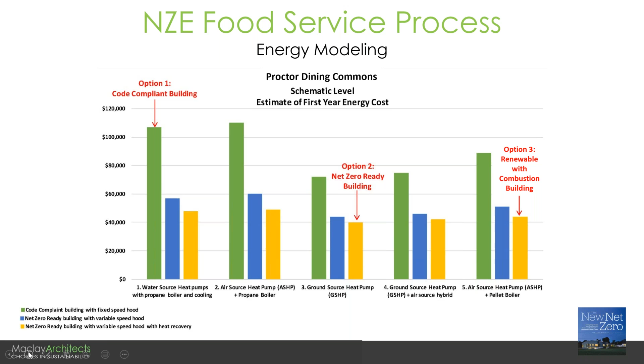So what does that look like financially? We normally look to make all of our net zero buildings cash flow positive from day one. We weren't quite able to do that on this project. The upper green line is the net zero ready and net zero building, and the blue lower line is with a propane boiler. When you start out, it's significantly more cost for the net zero ready option than for the propane one. However, in 27 years there's a break-even point, and then you start to buy down. For many clients, that may not be acceptable.